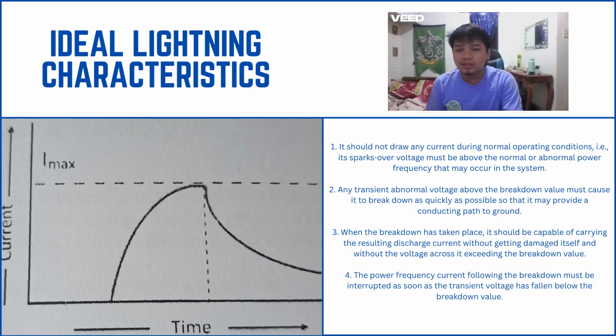Now let's go through the four main characteristics one by one. Number one, no current during normal conditions. An ideal lightning arrestor should not conduct any current when the system is operating normally. The second one, quick response to abnormal voltage. If there's a sudden high voltage or transient surge, the arrestor should immediately break down and provide a path for the excess current to safely flow to the ground.